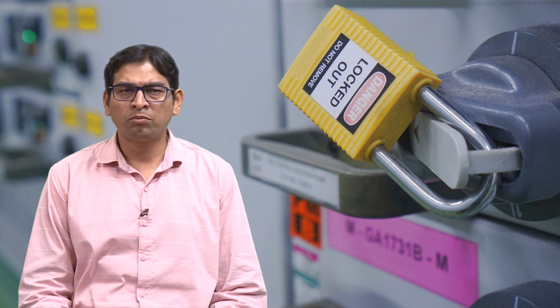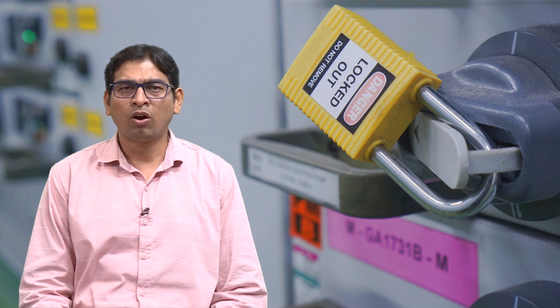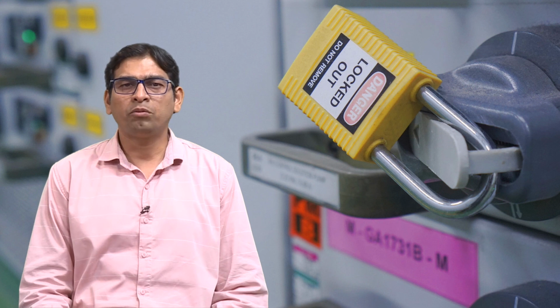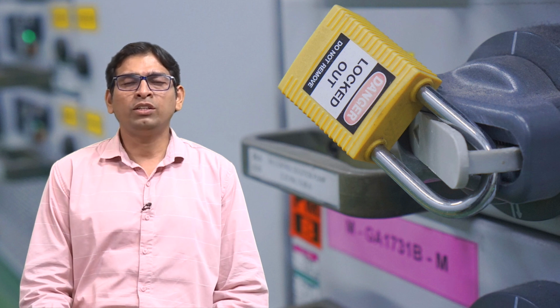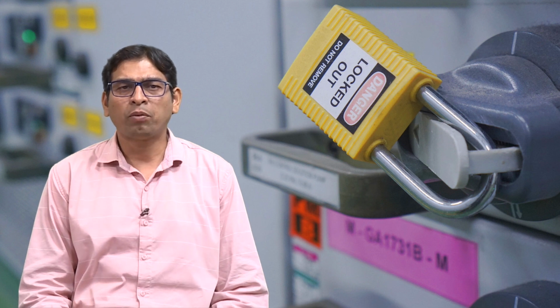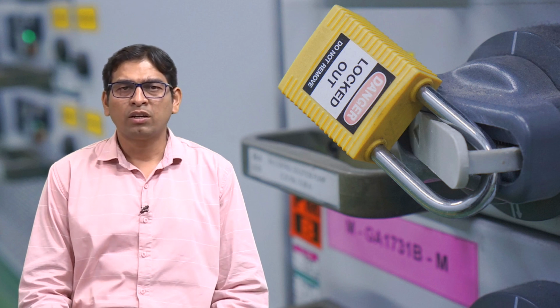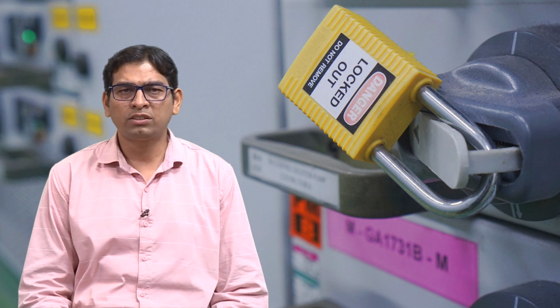After you complete your initial lockout tagout procedures, you may need to dissipate energy that is still stored in the machine that you are working on. How you do this will depend on the type of system you are dealing with. There are a number of techniques you can use for hydraulic or pneumatic equipment. You may have to adjust the valves or install blinds in piping to stop fluid from moving within the system. Electrical systems may require grounding to drain off stored electricity.